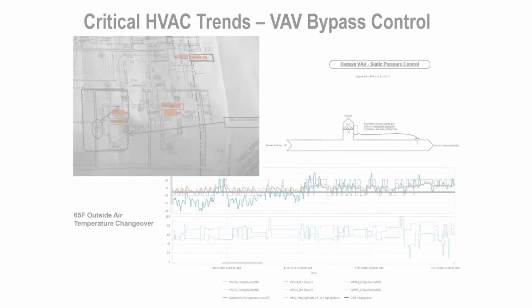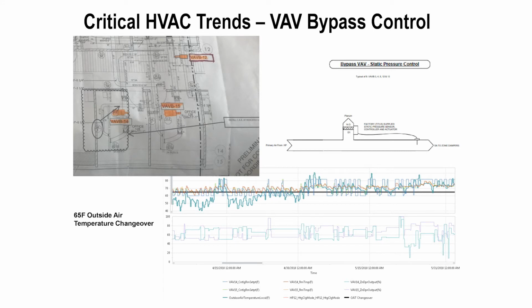All right. So this is simple to complicated. This is the system that we kind of mentioned. Essentially, what you have is a heat pump with two zones, with two independent thermostats. And each of those has a VAV box. If the zone is satisfied, that VAV box will close. There's a pressure independent box that relieves the air into the plenum when that box shuts off. So the heat pump stays at the same airflow the whole time, and it just relieves back into the plenum.